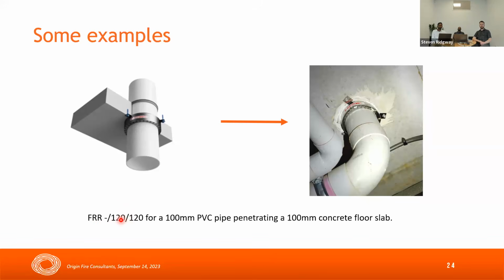In this case, for a 100 mm PVC pipe penetrating a 100 mm concrete floor slab, you get an FRR of -120, 120. But if, let's say, you drop this PVC pipe size to a 40 mm diameter PVC pipe, the fire resistance rating changes. It could be -90, 60. So manufacturers use a lot of products, like 40 mm pipe, 80 mm pipe, 100 mm pipe, and they test it, and then they give you the test results.